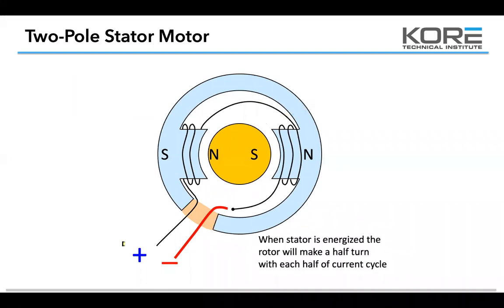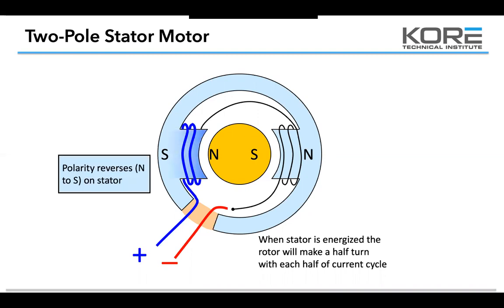When the stator is energized, the rotor will make a half turn with each half of a current cycle. So remember, when you're dealing with AC voltage, alternating current, if you ever look at a sine wave, it goes from positive to negative, and that's a cycle. That's what they're talking about, half that cycle. Everything in the United States is 60 hertz. So 60 cycles per second is what 60 hertz is. So that current's moving very rapidly per second through that conductor.